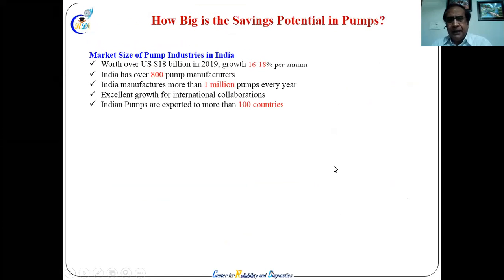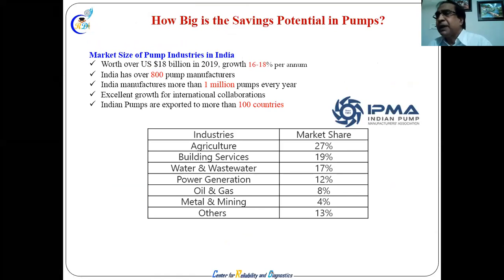So how big is the potential? Is the potential of pumps too much? That day also I told you, 800 pump manufacturers here, 18 billions worth, 16-18% growth in pumps, and pumps are everywhere in industry, industry is full of pumps. There is potential of saving too much, and it is not being saved. How will you save it? Maintain it properly, operate it properly. That is the only saving. If you cannot do that, no VFD, no other thing is going to give any energy saving at all.